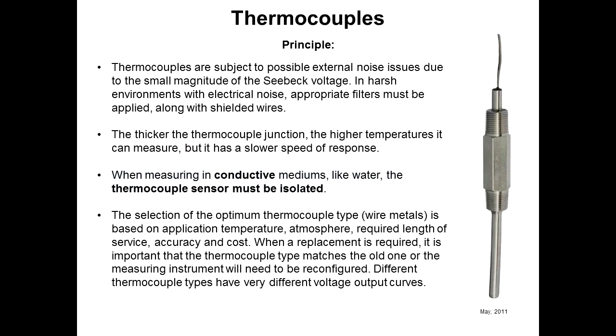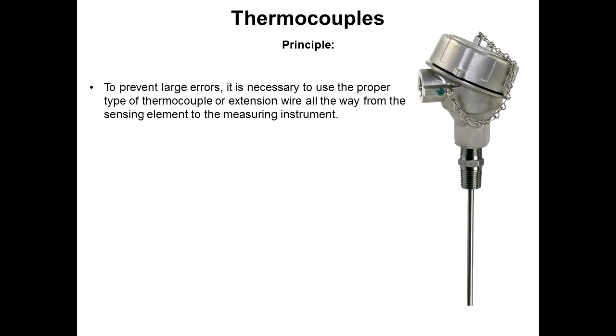The selection of the optimal thermocouple type wire metals is based on application temperature, atmosphere, required length of service, accuracy, and cost. When replacement is required, it is important that the thermocouple type matches the old one, or the measuring instrument reading that thermocouple has to be reconfigured to a different type. Different thermocouple types have very different voltage output curves. To prevent large errors, it's necessary to use the proper type of thermocouple or extension wire all the way from the sensing element to the measuring instrument.